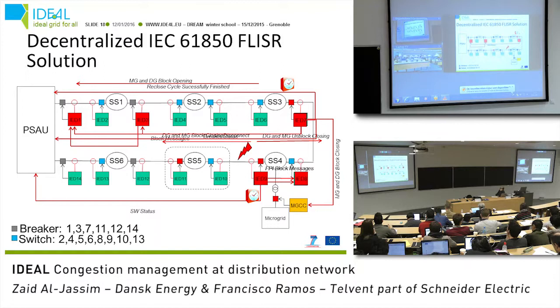So after that, the fault will be cleared, and we will send different messages to update the status and allow the microgrid or distributed generation, and block disconnecting the distributed generation here to avoid islanding operation. After that, we will repeat the process, but at the switches level.